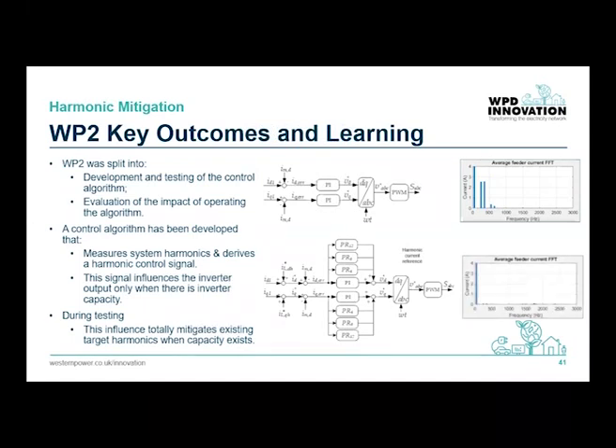As a result, testing has shown that the upstream feeder current harmonics are virtually eliminated when the harmonic controller is switched on and sufficient inverter capacity exists. Analysis of the feeder current shows the 5th, 7th, 11th and 13th order harmonics are all but absent when the controller is in operation. From testing, we also demonstrated that harmonic mitigation is limited during periods of higher fundamental power conversion. So the next key question was, what impact does the controller have over a longer time period where the inverter's capacity to act on harmonics varies?